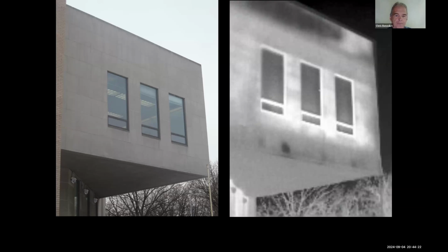So you see the white is brightest under the windows because there's a heater there. And that's the right place for a heater to be, by the windows. But you see the top right hand corner of the structure is also white. Most of the top, for about 4 feet of height, it's black, so it's colder than the rest. So what's going on there is, with the exception of the white part at the right toward the corner of the building, the parapet is cold.